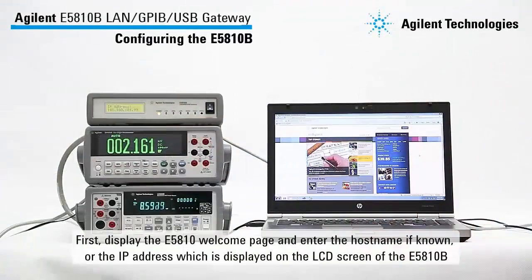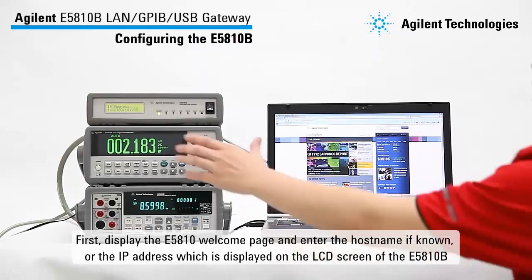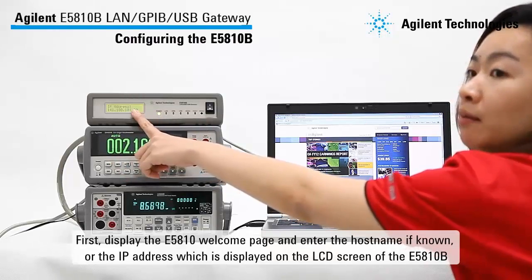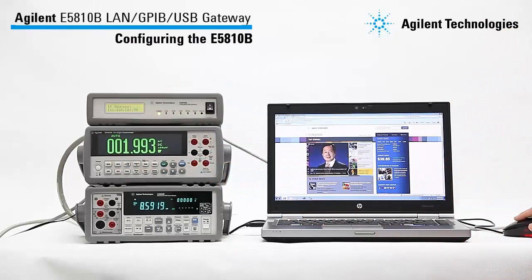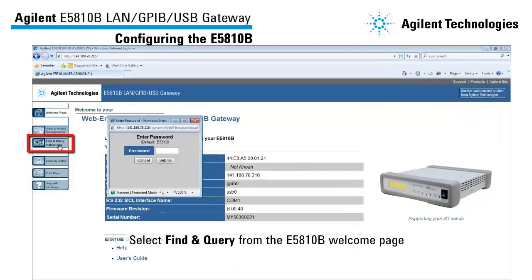First, let us display the E5810B welcome page. Open the web browser and enter the hostname if known, or the IP address. In this case, I will enter the IP address which is displayed on the LCD screen of the E5810B. To verify that we have connected the E5810B to the network, select Find and Query from the E5810B welcome page.